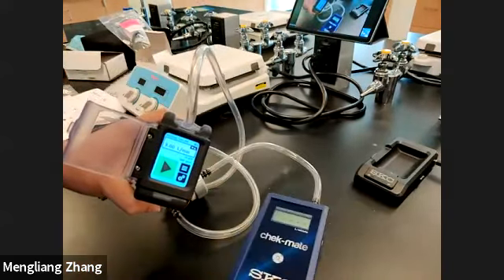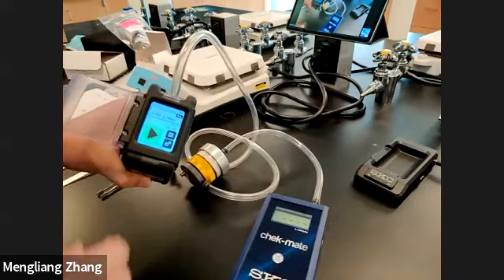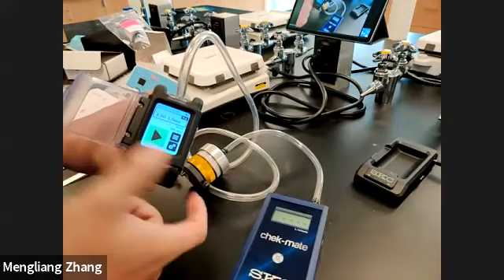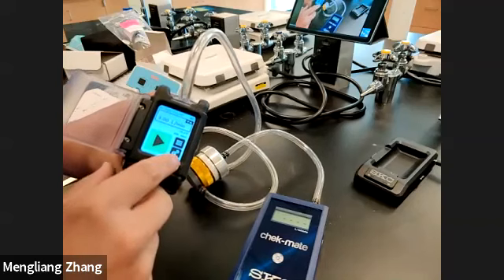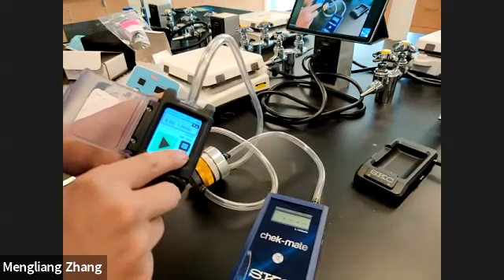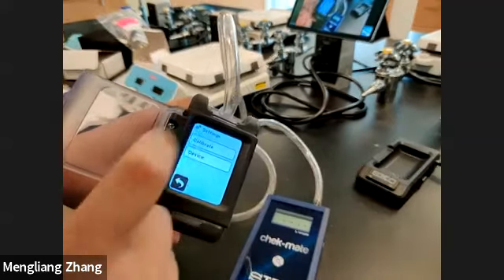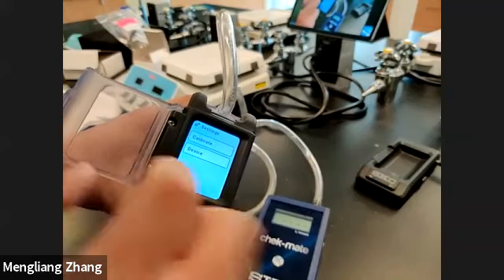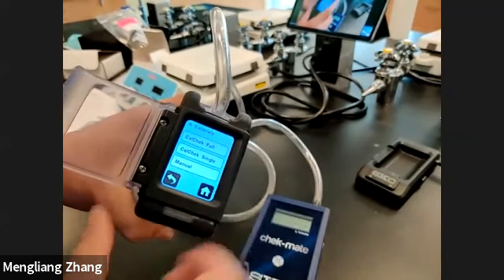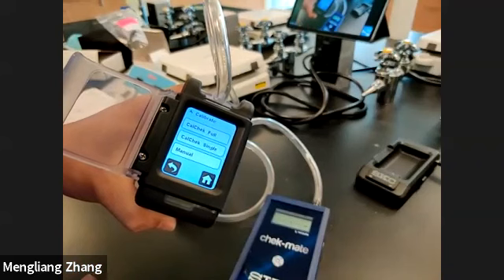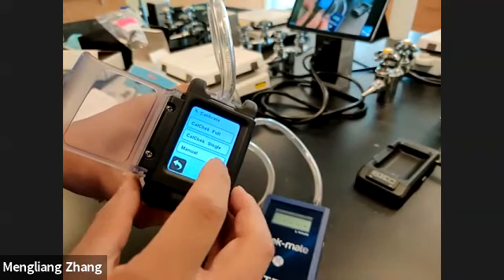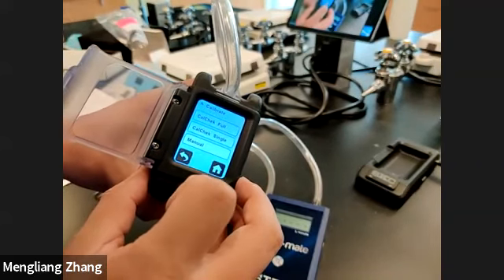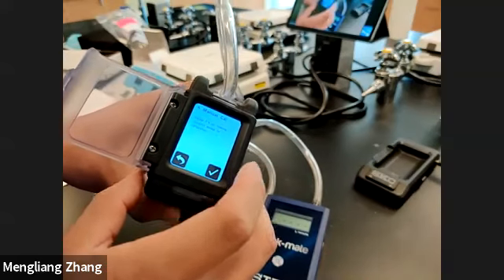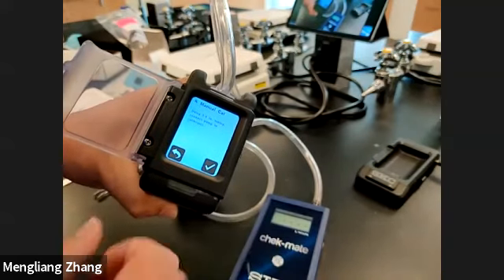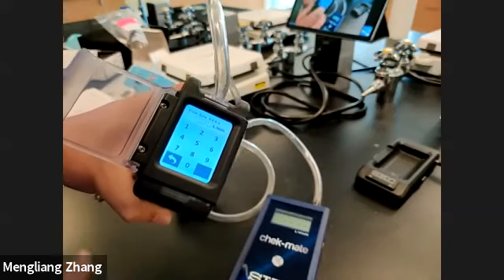We want to calibrate the airflow at 3 liters per minute. So at the setting icon, we click setting, and then the top option is calibrate. So we just press calibrate. In this case, we want to calibrate the airflow manually, so we press the last option, which is manual. We press manual calibration, and then we click OK.